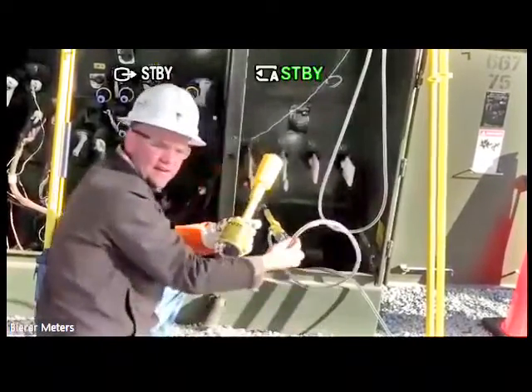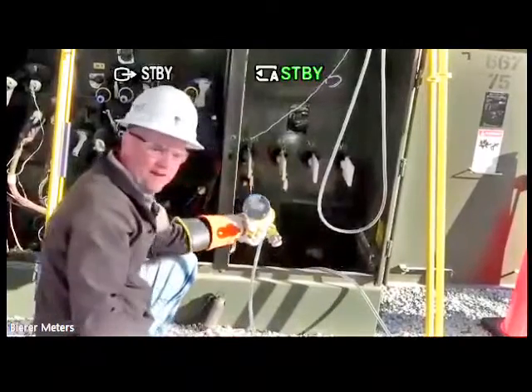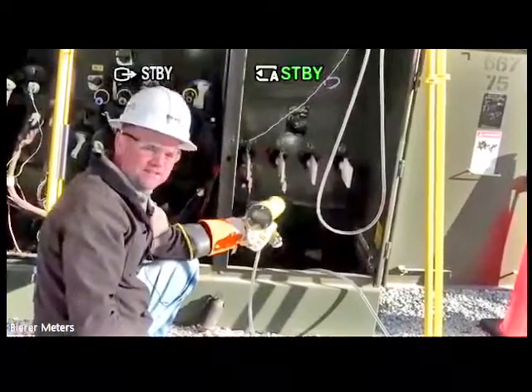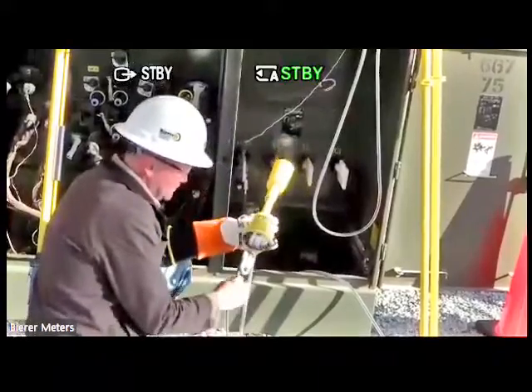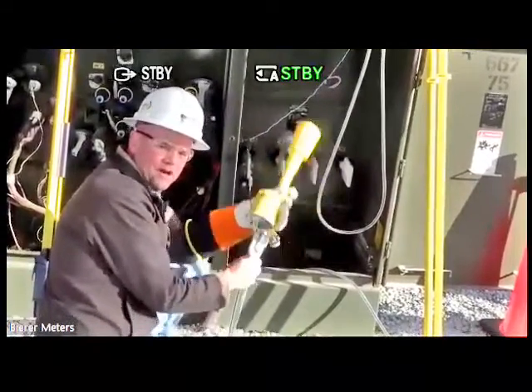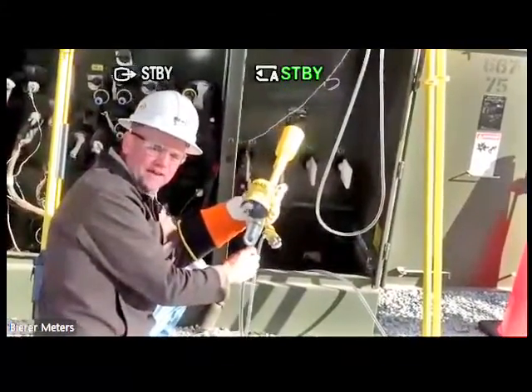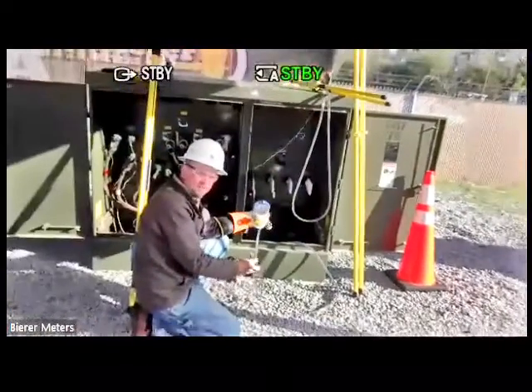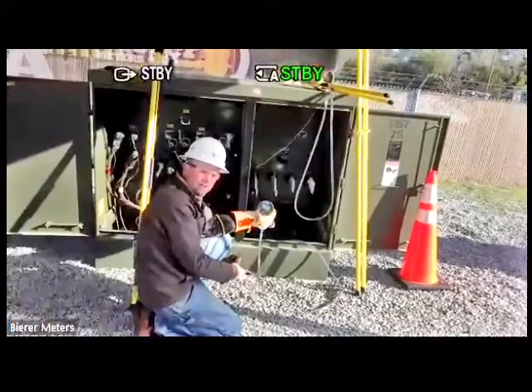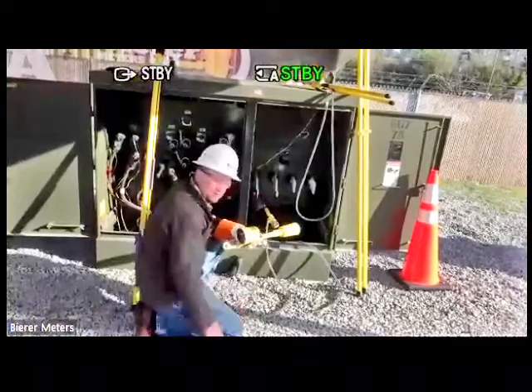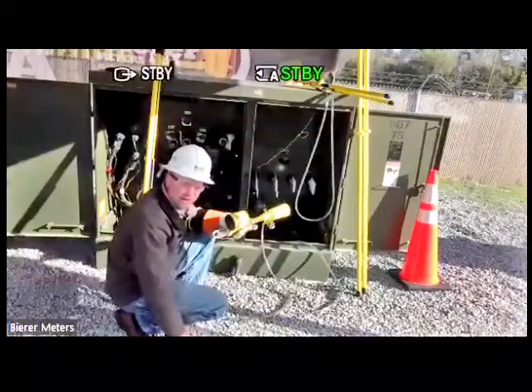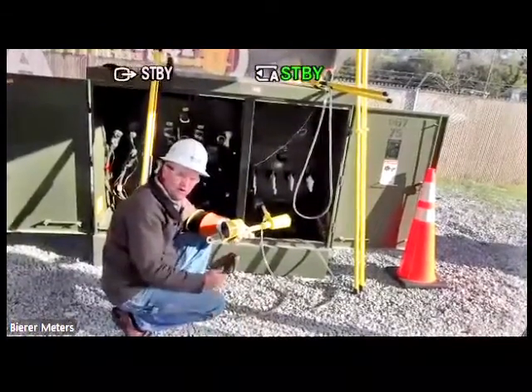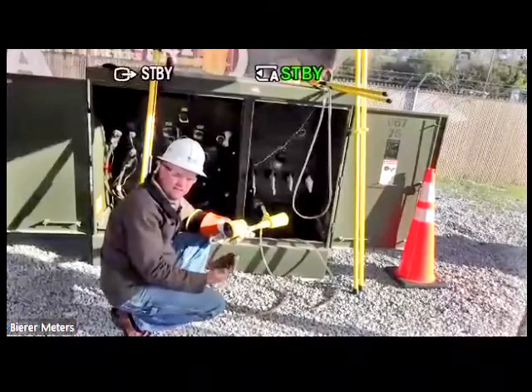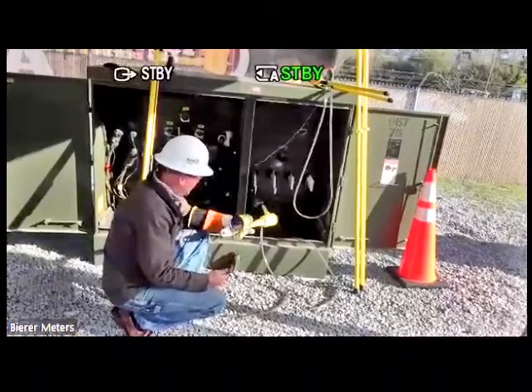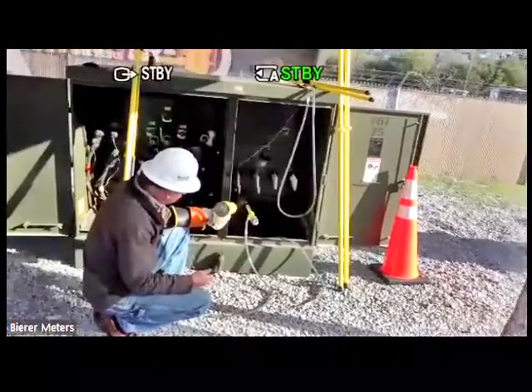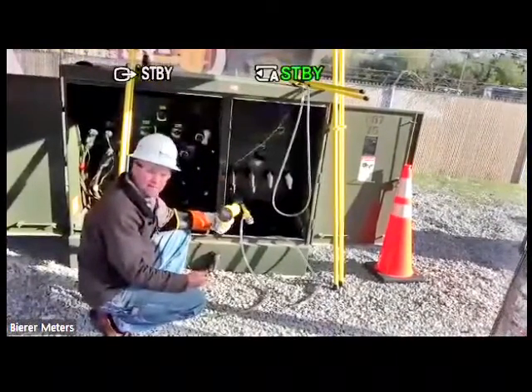If I use this scenario where I have 25 million ohms in series and I do that same thing, I attach to my meter probe and I overshoot and I go to a phase, I have some protection built into this circuit. So keep that in mind. We encourage people to use a second probe whenever they do this, whether it's underground or overhead, obviously, just because it's a safer method. And again, you can utilize any type of clamp.